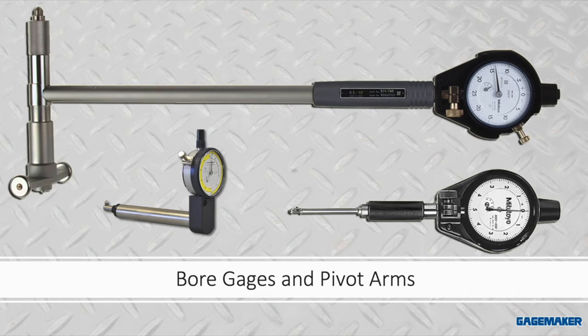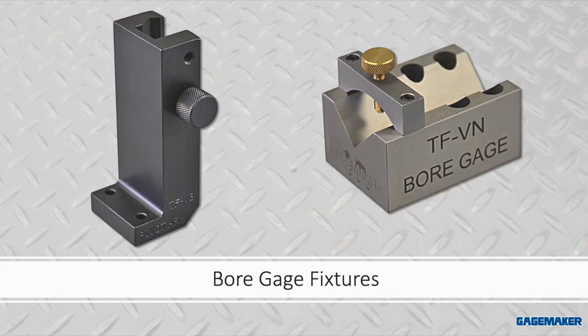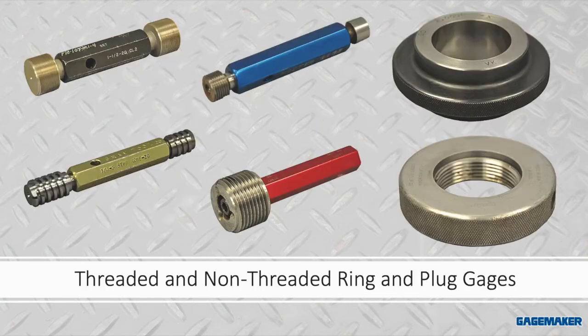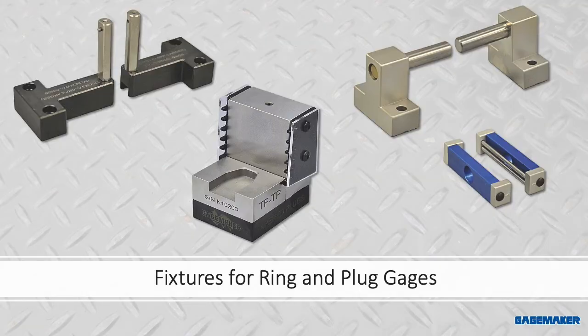For bore gauges and pivot arms, we use a TFVB or a TFVN fixture. One is a V-shaped clamp to hold the pivot arm style instrument, and also the TFVN is a V-shaped base for 2-point bore gauges. For straight plugs, the TF2R precision anvils and the respective thread wires and holders are used during calibration. For a tapered plug, the TFTP fixture has a slanted base for proper orientation. And for threaded rings, the TFSP fixture is perfectly suited with probes and ball contacts designed to ride in the helical path of the ring gauge. All these can be used in combination with multi-axis support tables for the most accurate results.